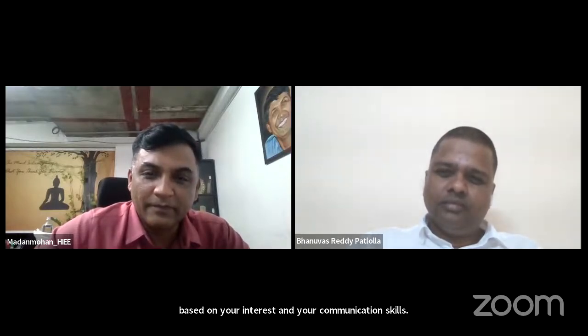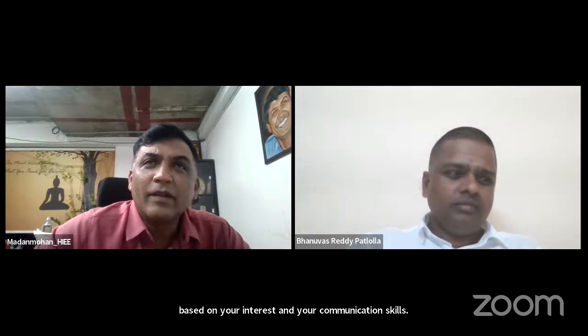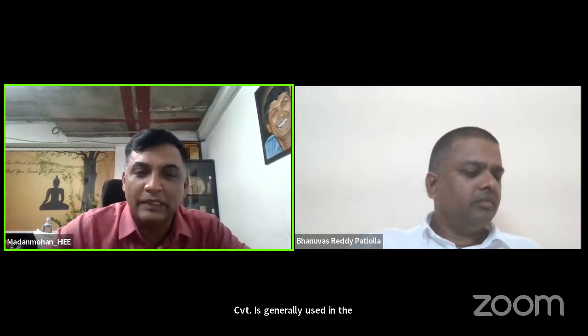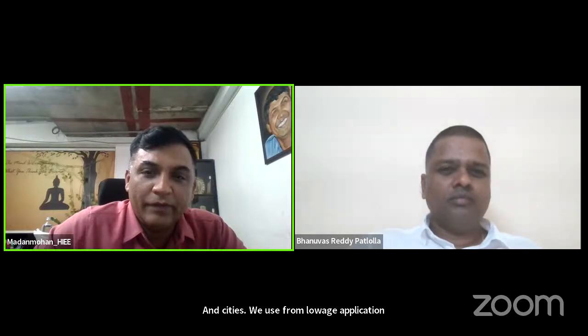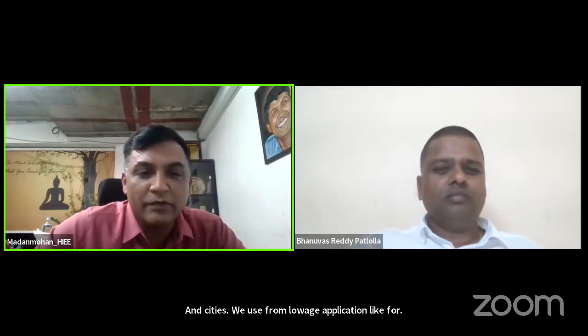There's a question from Rajesh. For what voltage levels do we use PT and CVT? CVT is generally used in the transmission system, from 132 kV and above. And the CTs we use from low voltage application, like from 415 V to 765 kV, we use current transformers.